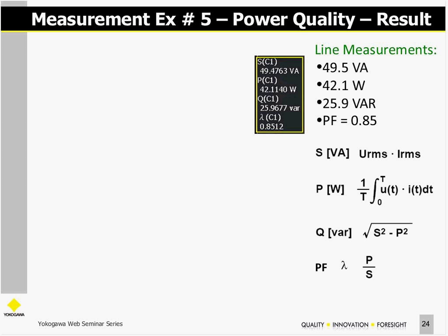Here's a graph of just several cycles of steady state voltage and current input, and then instantaneous power, I times V, plotted at the bottom. In this case, total power S equals 49.5 volt amps. Power calculated, P, on channel 1 is 42.1 watts, Q is 25.9 VAR, and the power factor is 0.85, which certainly is a decent power factor by standards.